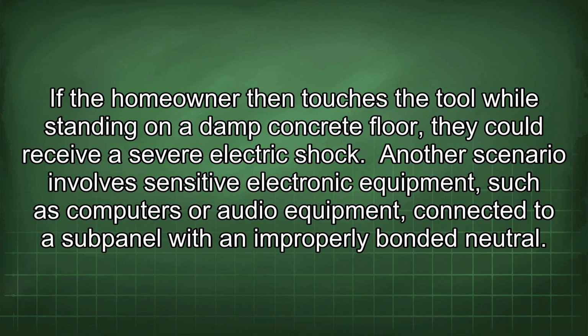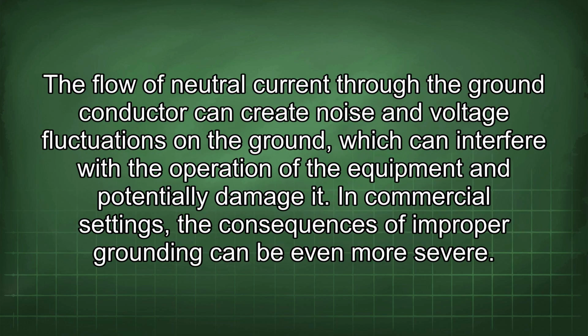a severe electric shock. Another scenario involves sensitive electronic equipment, such as computers or audio equipment connected to a subpanel with an improperly bonded neutral. The flow of neutral current through the ground conductor can create noise and voltage fluctuations on the ground, which can interfere with the operation of the equipment and potentially damage it. In commercial settings, the consequences of improper grounding can be even more severe.